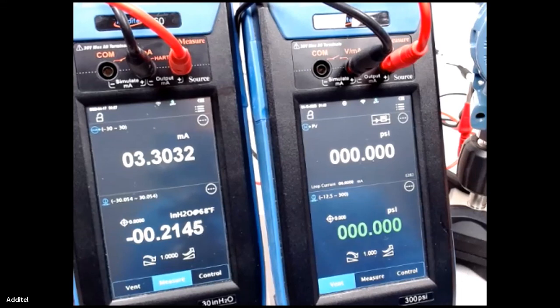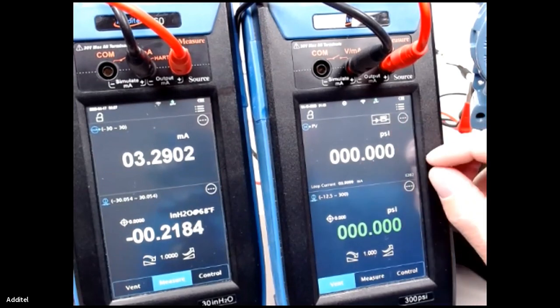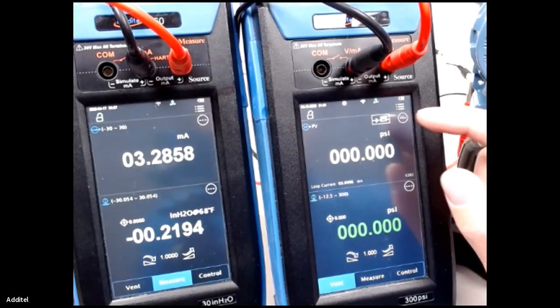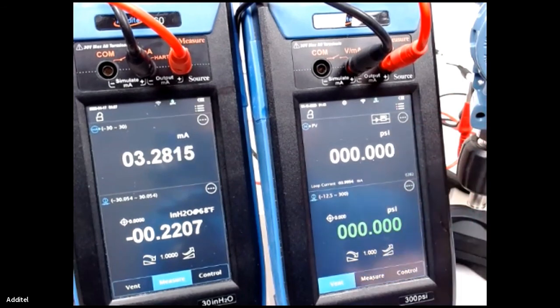I think this is one of the really cool features about this unit that maybe a lot of people don't use, and that's the HART functionality. It makes this unit really a good deal, because you can literally take one unit out in the field and adjust your HART transmitter, pressurize it up, do everything, which in the past you've had to take two or maybe even three units out to accomplish that task.